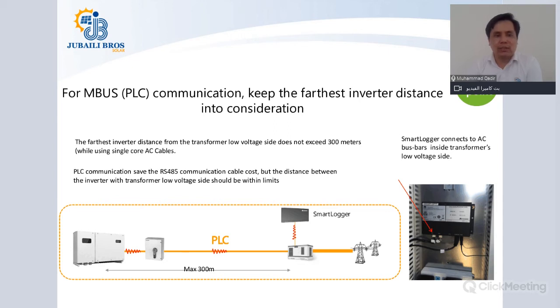Okay, so talking of this MBUS communication or the PLC, you must take care of the farthest distance between the inverters. The farthest inverter in this type of connection should be at a maximum of 300 meters when you are using single-core AC cables, because your communication will be done through the AC cables. We modulate the communication signal on top of your power cable on the two phases, which is then demodulated at your smart logger end, and read from the smart logger point.